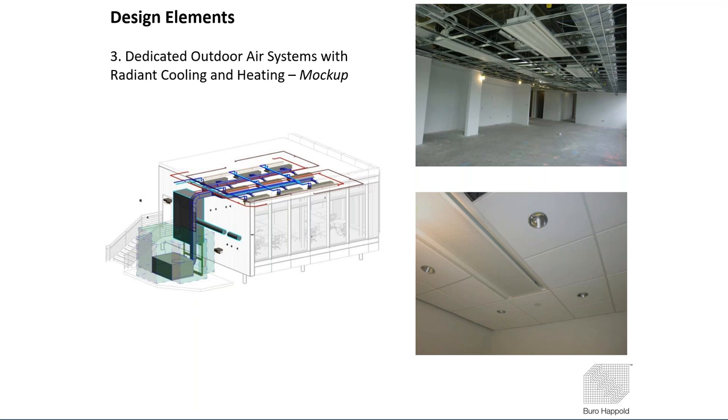I had another project, I mentioned this yesterday, a lab project where we were trying to do chill beams, and the load in the space was a little higher than what we usually saw, so we wanted to place the chill beams closer to each other. First we did a CFD analysis, and then we mocked it up in Winnipeg with Price to make sure that the airflows coming out of the chill beams weren't going to crash into each other and cause downdrafts.